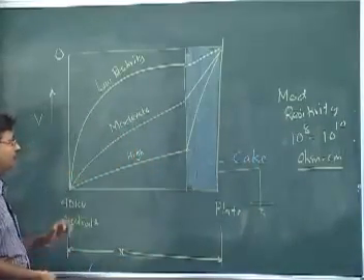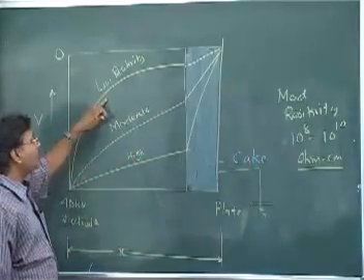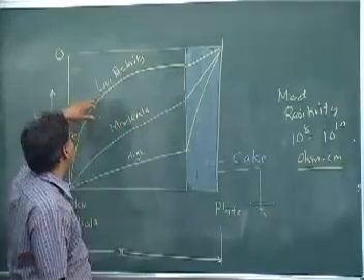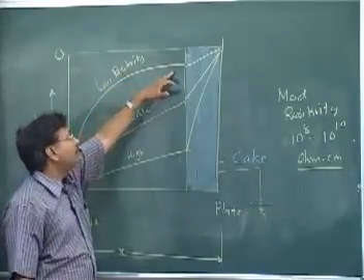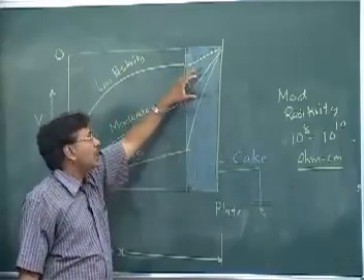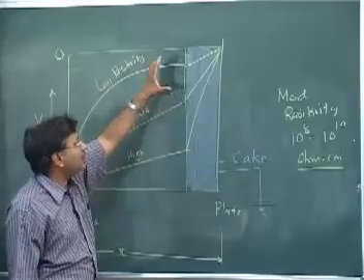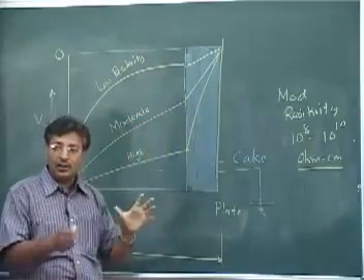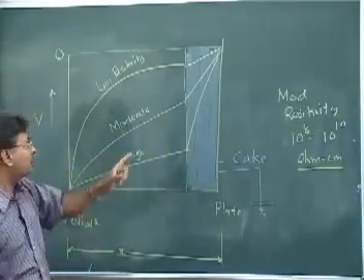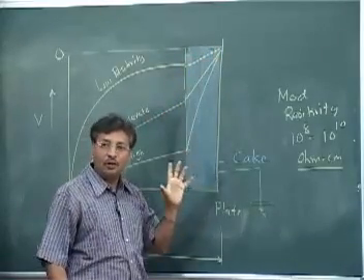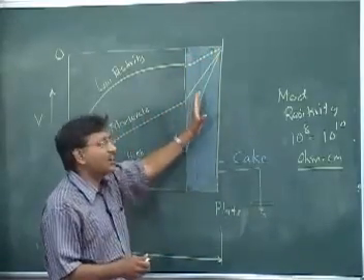See here, when resistivity is very low, there is not much difference of voltage between here and here. As a result, even if the particles are trapped, there is not enough force for them, because things are about the same at this point and this point. So they have not enough force to stick onto this one.